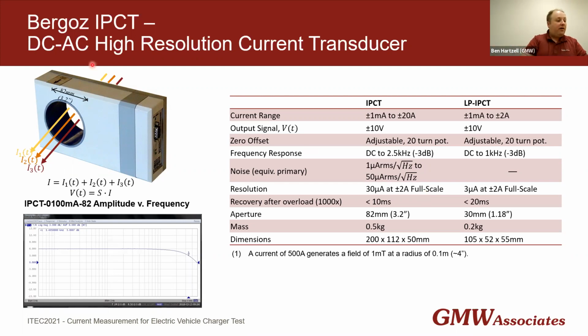And you can see here on our drawing, we've shown 3-phase I1, I2, and I3, so 3-phase power passing through. And so this is going to measure the total current of all 3 phases. So I total is I1 plus I2 plus I3. We then get a voltage signal output equal to the sensitivity times I total, again, all 3 phases. And so if there is some sort of leakage or loss, this very high resolution will allow us to see it, the very low noise.